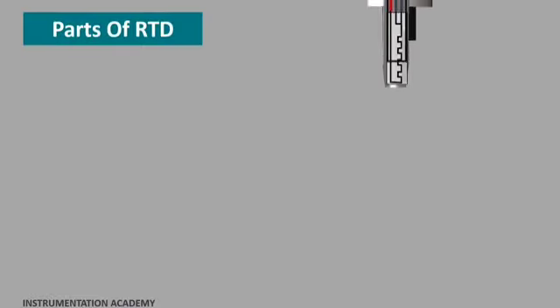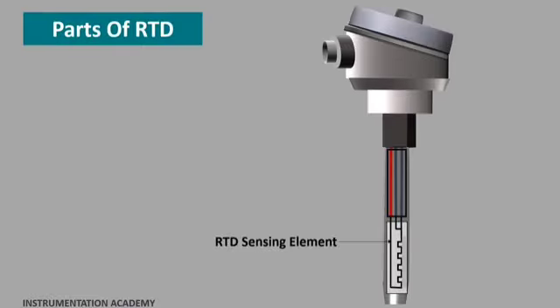Parts of RTD. Sensing element or RTD element. The sensing element is the actual temperature sensing unit, which is located at the tip of the temperature sensor on the end that is exposed to the process temperature. The sensing element, which is constructed of metals like platinum, nickel, copper or tungsten, responds to the process temperature by generating a measurable resistance.